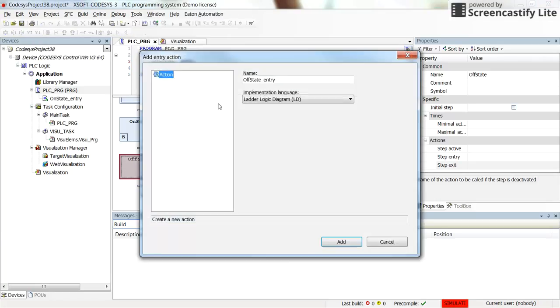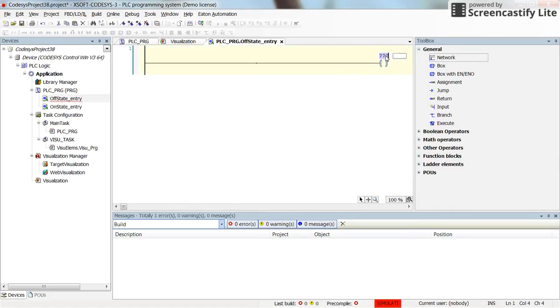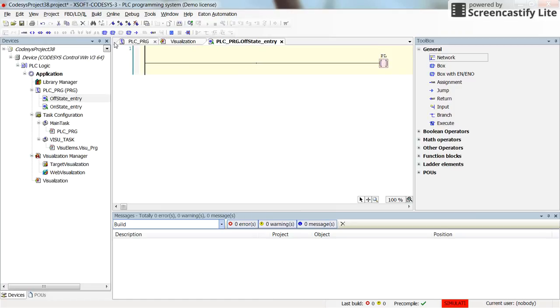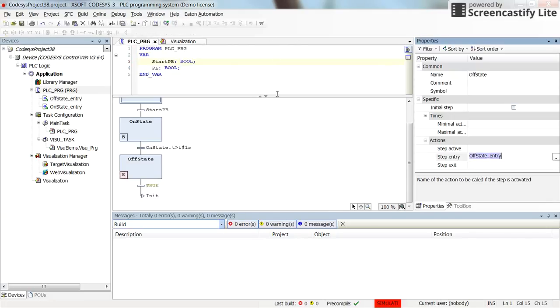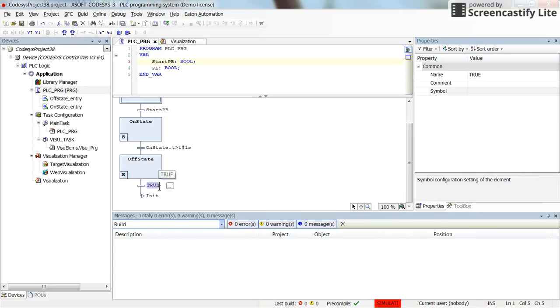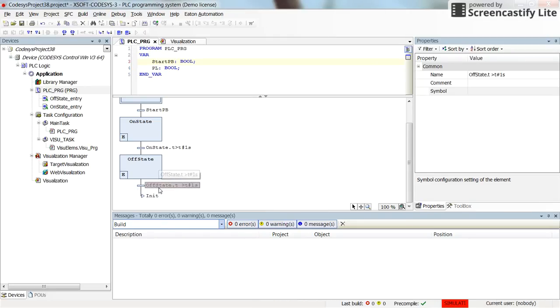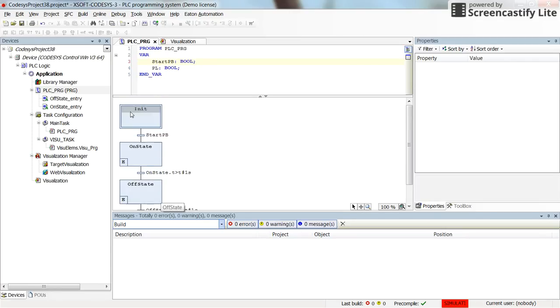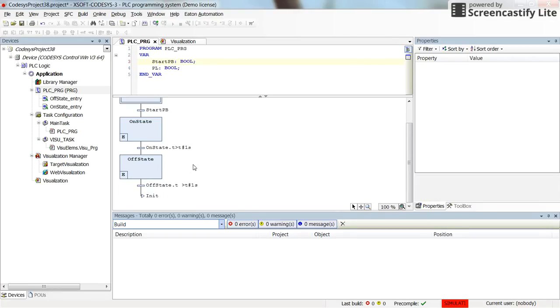I'm going to determine another entry action for this with the ladder logic. And in this case, I'm going to turn off the pilot lamp. So here we will have PL. And for this I will have the negated coil. Alright, and then I want to have the pilot lamp turned off for another one second. So here instead of true, I will write off_state.t bigger than one second. If this is the case, then the transition will happen and then the execution will jump to the init. And then the process will start again.